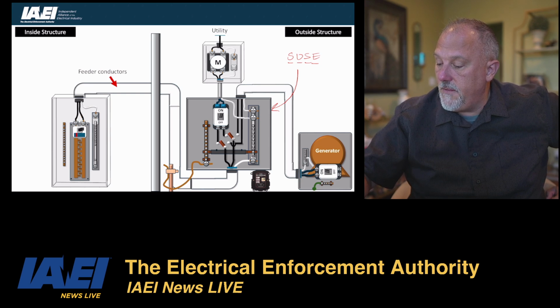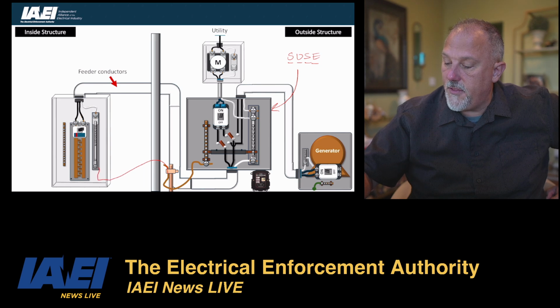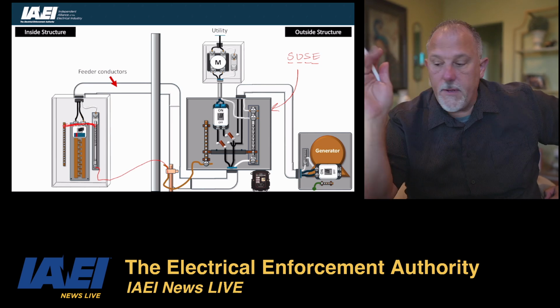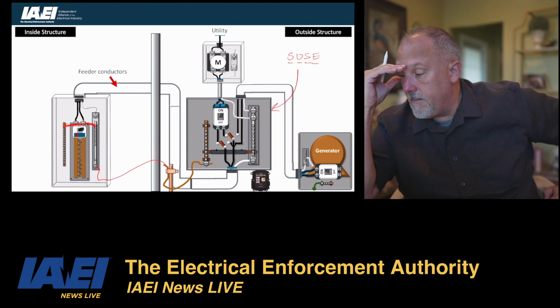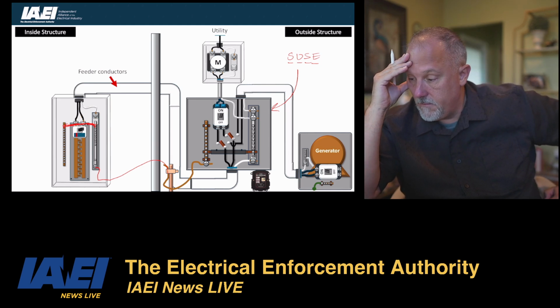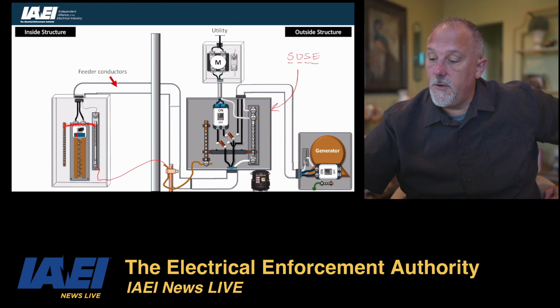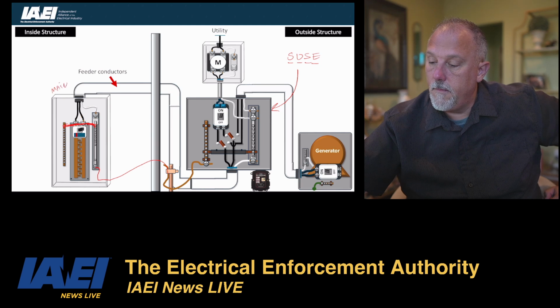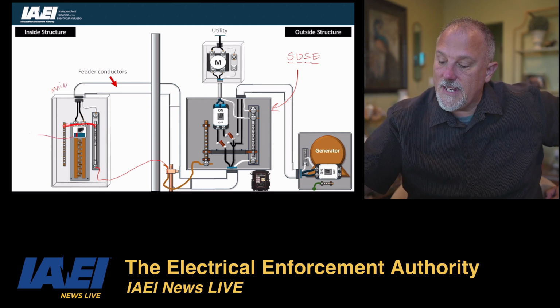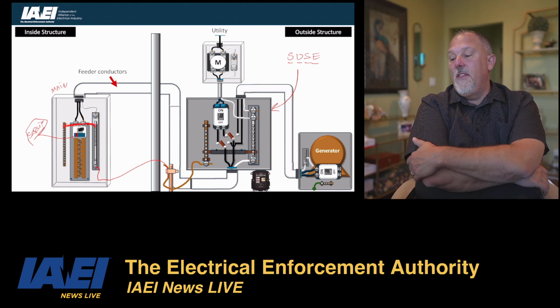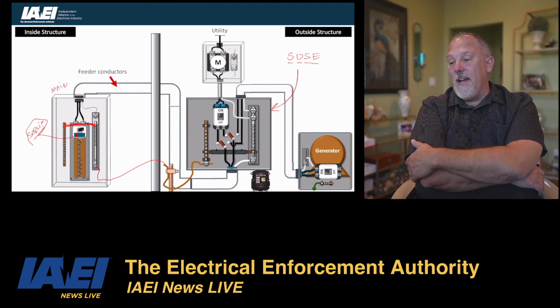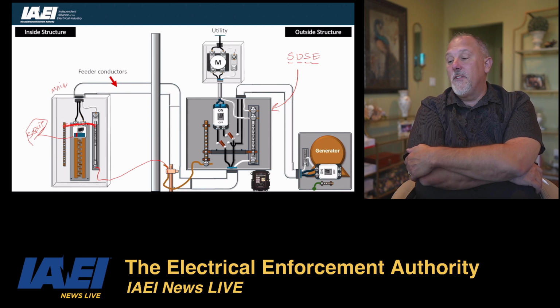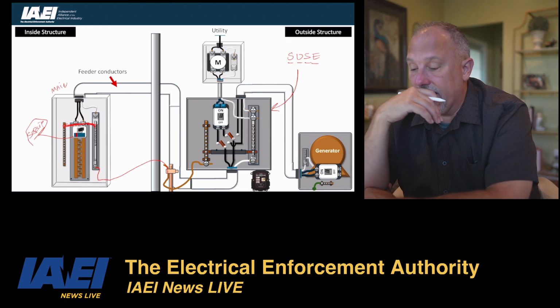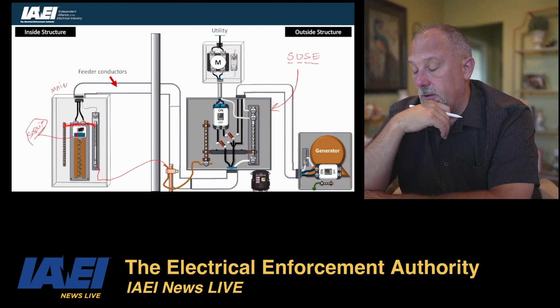you could leave this grounding electrode tied in with the actual service and leave the equipment, and this is still your main panel. And I was going to say leave this as a service disconnecting means, but you can't, because those are not service conductors. It would be feeder conductors. No matter what, those are always going to be feeder conductors. That would just be your main circuit breaker for the panel.